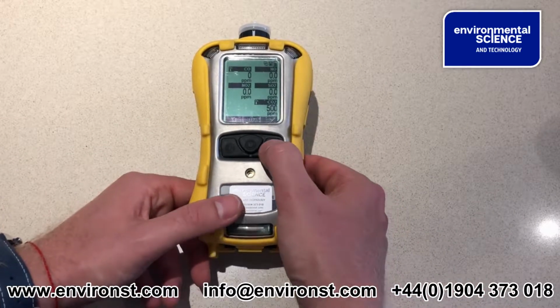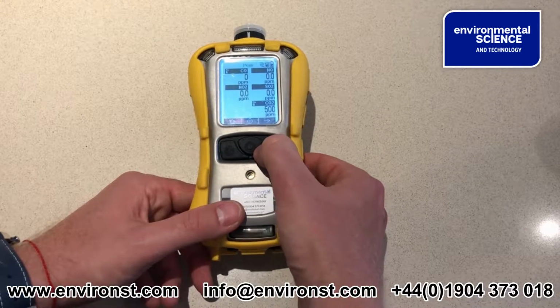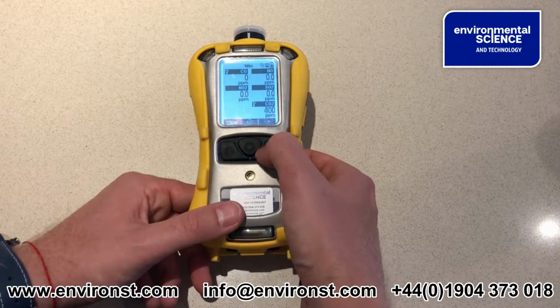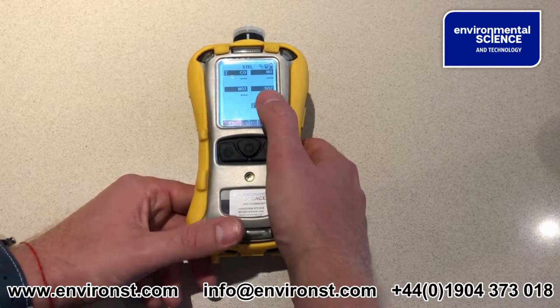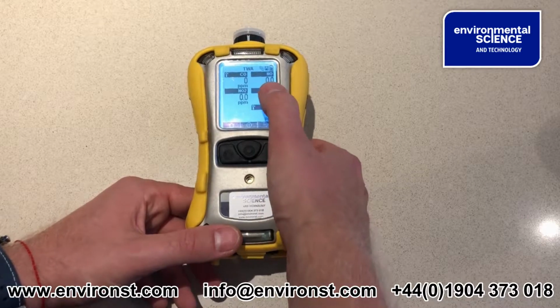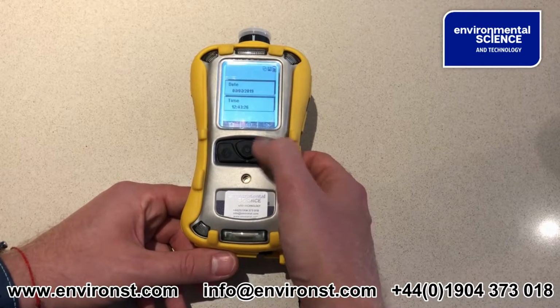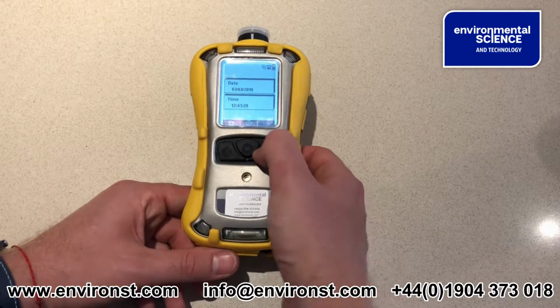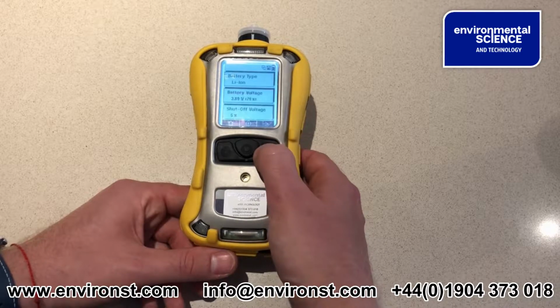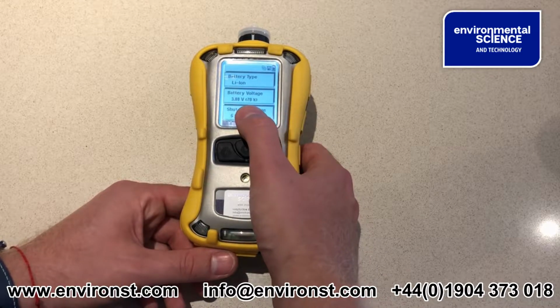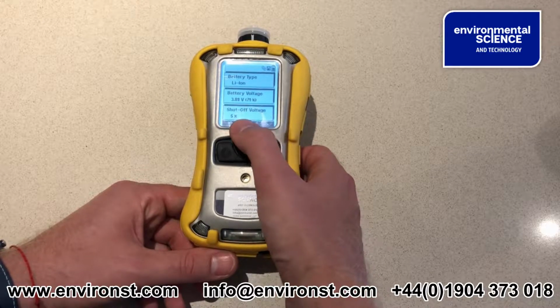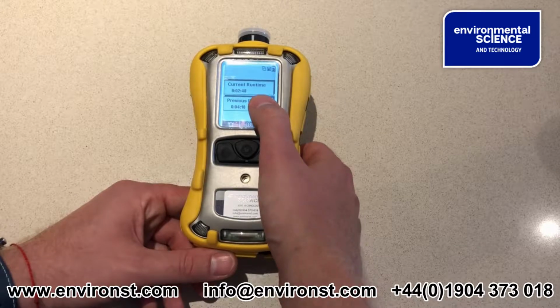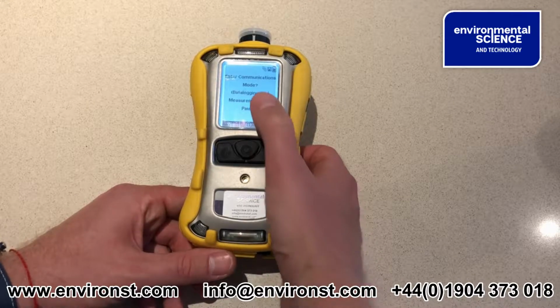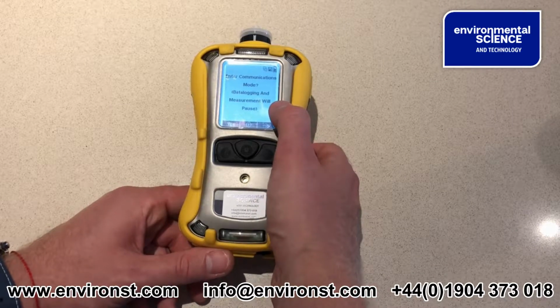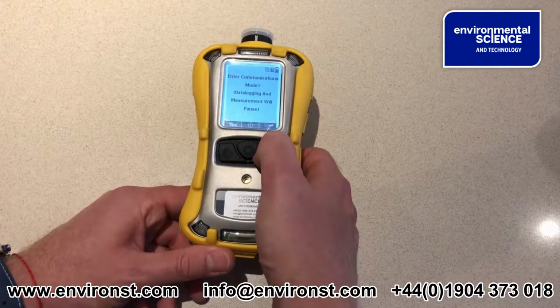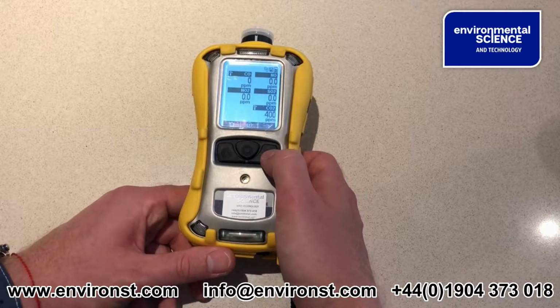If we want to scroll through different screens, we can press this across arrow here, and this screen gives me peak values, minimum values, STELs, so short-term exposure limits, and time-weighted averages, so longer-term exposure limits. It gives you the date, the time, current temperature, your lithium-ion battery, the battery voltage and percentage charged, and the shut-off voltage, how long it's been running for, the previous runtime, and this is where you can put the unit into communications mode for hooking up to a computer. And now we're back round to the original screen.